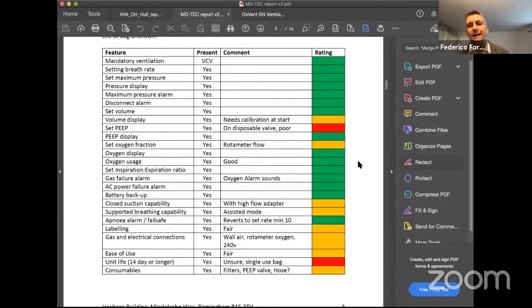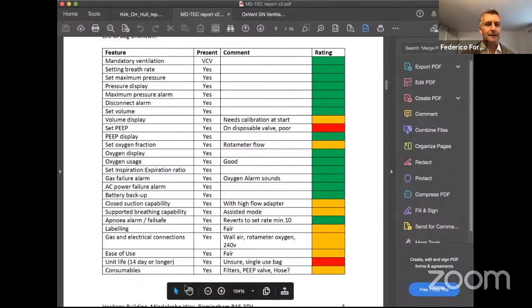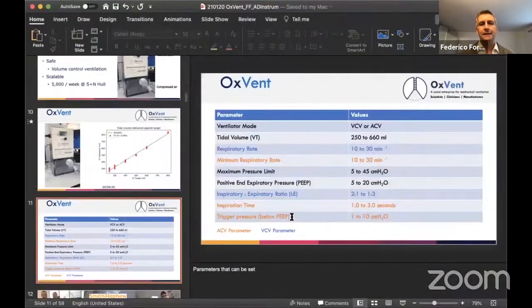So, can this ventilator be used for pediatric use? I do not think it can, and the reason for that is the respiratory rate that it can deliver. If we look at this slide here, the respiratory rate range is from 10 to 30 breaths per minute. My understanding is that in pediatric scenarios we need more than 30 breaths per minute, and possibly also smaller tidal volumes. This design does not work in pressure control mode. It is especially, I think, in Europe, a preferred mode of ventilation, but this current design does not deliver pressure control ventilation.